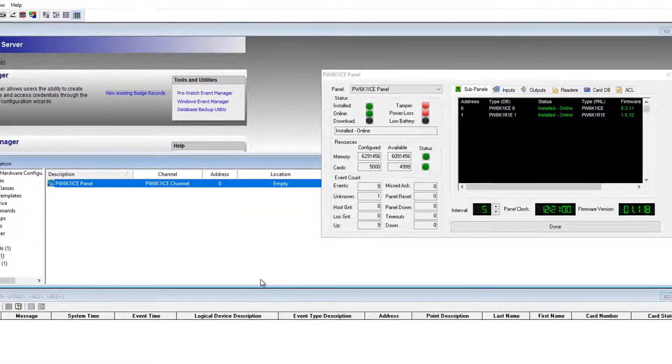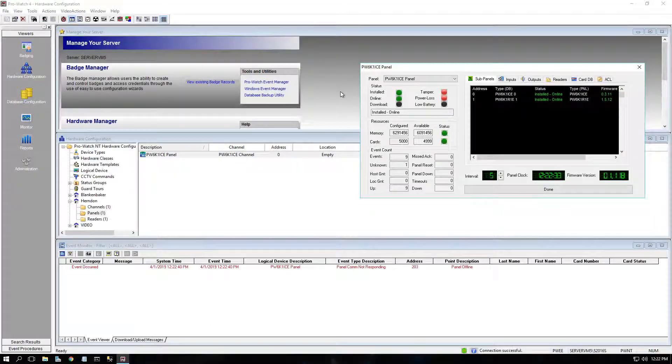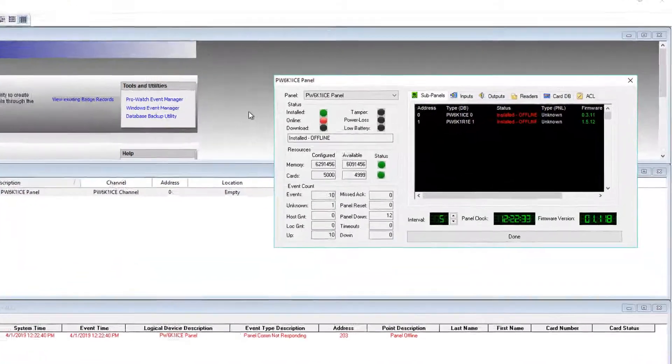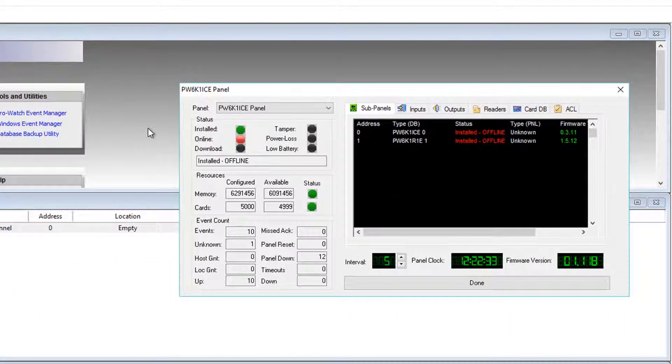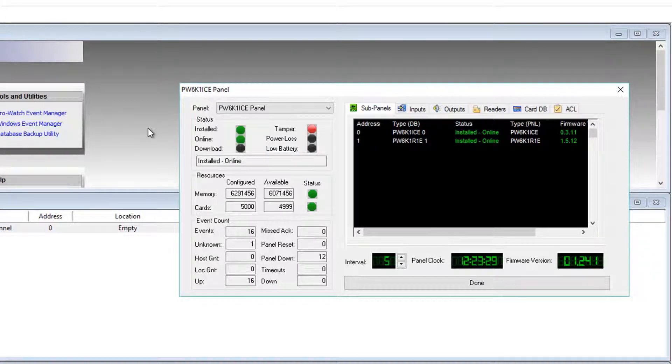The download firmware process may take anywhere from just a minute to maybe a few over five minutes. We'll see the controller drop offline in status as indicated by the red LED, and then once back online, the firmware version at the bottom right will show updated. In this example, 1.24.1. Step one is complete.